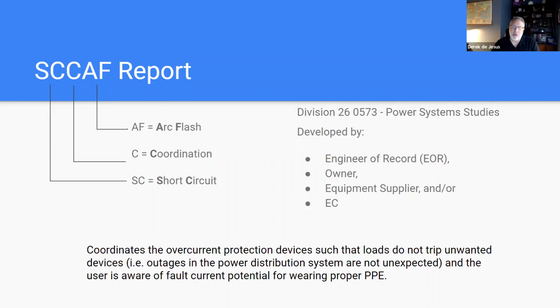Well, one, we develop them because code NFPA 70E, as well as OSHA, require that this analysis and study be performed for your project. But for an owner, for reliability and resiliency, you want to ensure that all of the overcurrent protection devices are properly coordinated so that when you have a short circuit fault downstream, like on a panel board, or you have a phase fault on a conductor, you're not going to trip your main incoming breaker, right? You want to trip the next available overcurrent protection device. So you want to keep your system up and running. And that's why you do a short circuit study analysis.